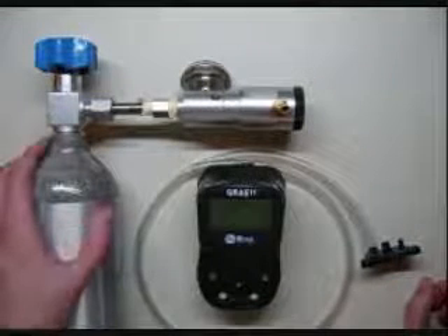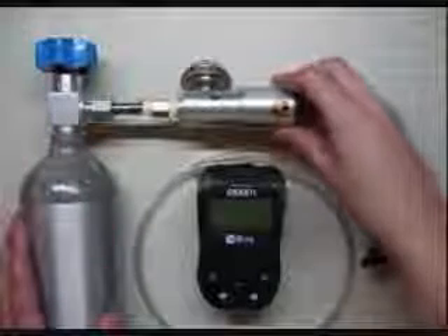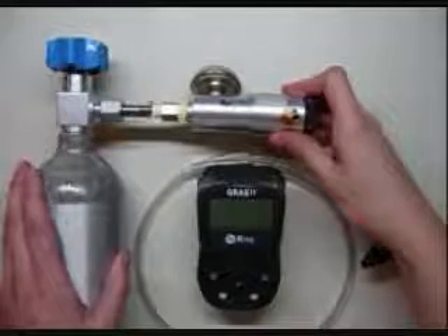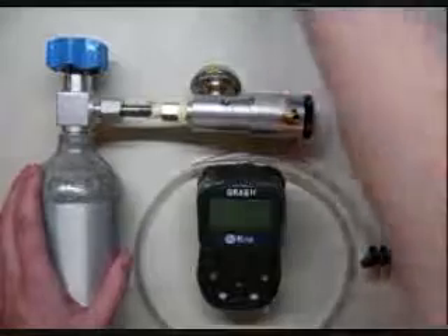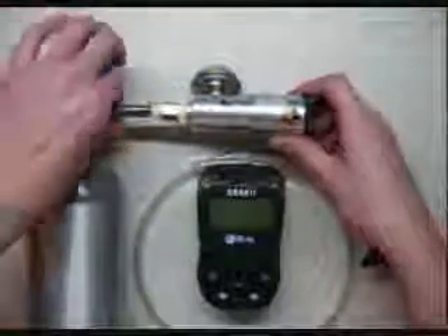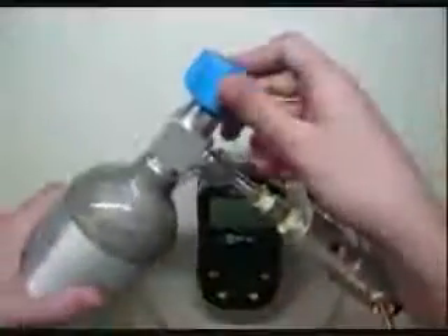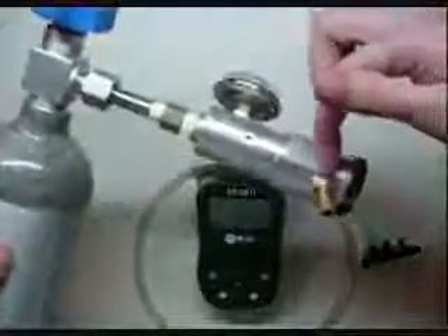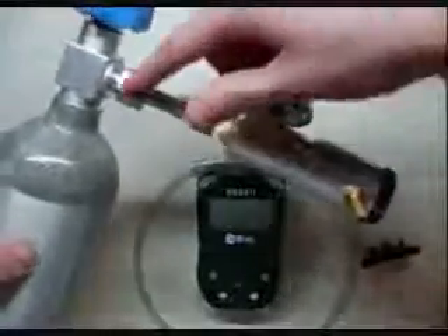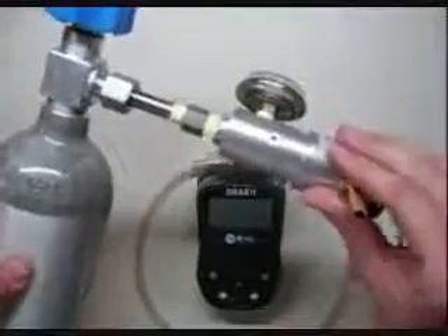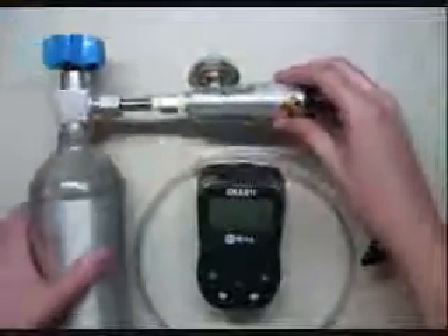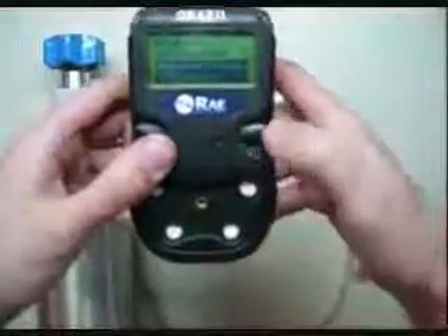Now with this cylinder of cal gas here, I don't have a normal disposable. What we're using is this one, which is a refillable cylinder. The same standards are still going to apply though. When you first screw this in, you're going to want to make sure that you have this open. Right now it's a 0, meaning there's 0 flow going through it. But normally you're going to want to leave it open and then unscrew this portion here. What will happen otherwise is all this empty space here, which is filled with the room air, when you open this, if you have this closed, will fill with calibration gas and mix with the room air, and it'll distort your values in there.